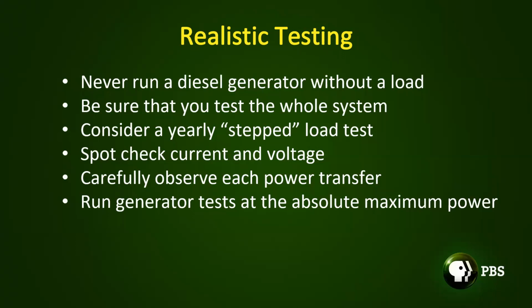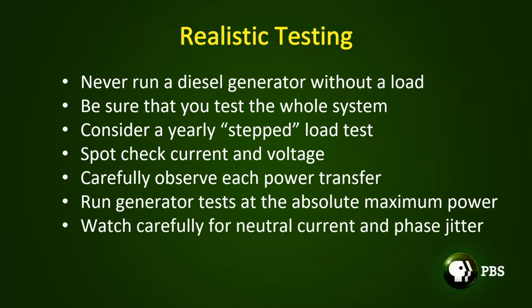So once again, when you're running your monthly test, do everything you can to make sure that there's not anything in the facility that's going to switch on and push the generator beyond its load capacity. And this is the last one. This one is something you'll learn the hard way sometimes, and that's to watch very carefully for current in the neutral and for jitter between the phases. Those are things that can really cause problems, and subtle problems, with circuit breakers and contacts and electronic equipment. And the only way you can catch them is to check the neutral currents and phase jitter each time you run your monthly test. So those are my suggestions for realistic testing.